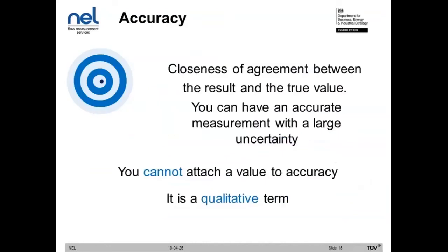We also have to define what accuracy means. This is a very common term, and it's not always used in a technically correct way. Accuracy refers to the closeness of agreement between the measured value and the true value of the measured parameter. It's possible to have an accurate measurement despite the fact that you're operating with a high measurement uncertainty.